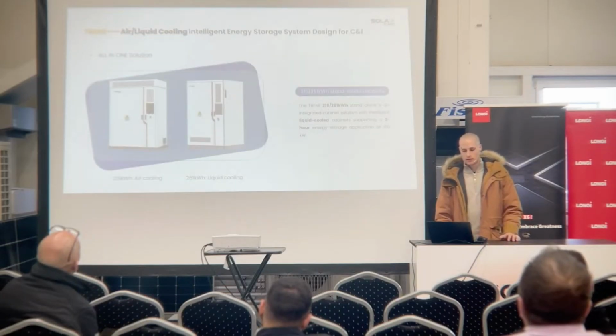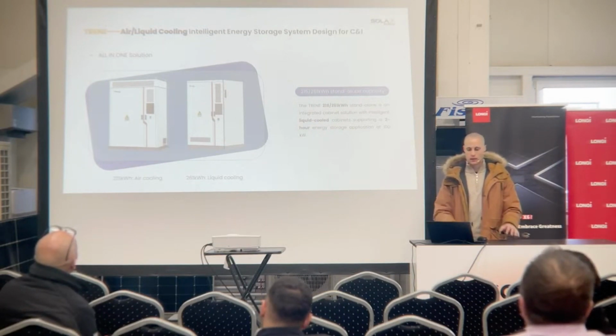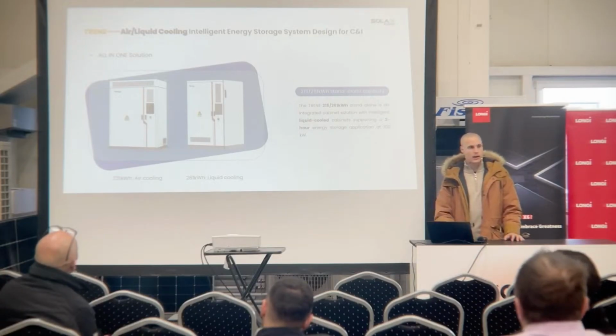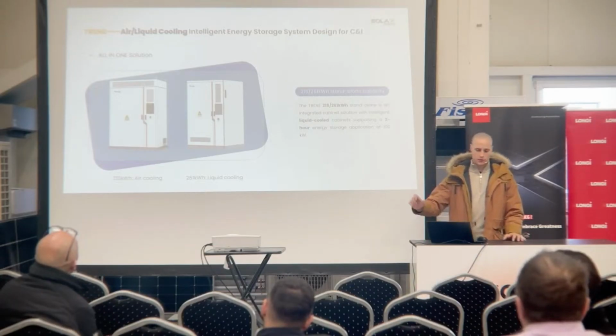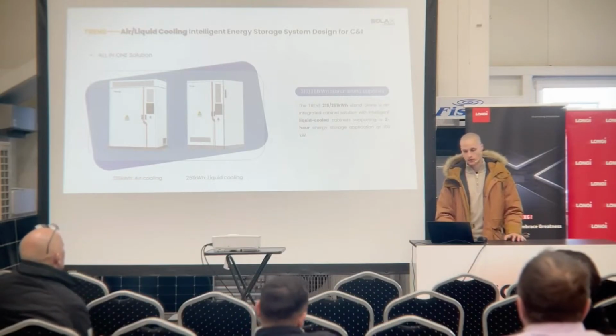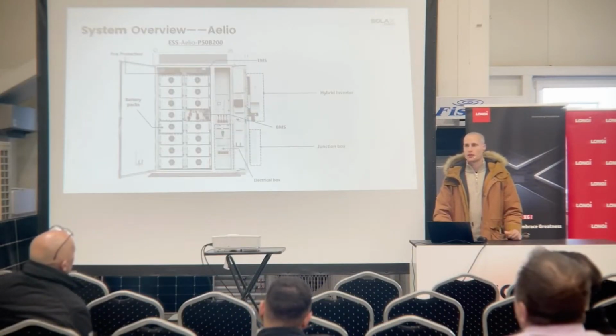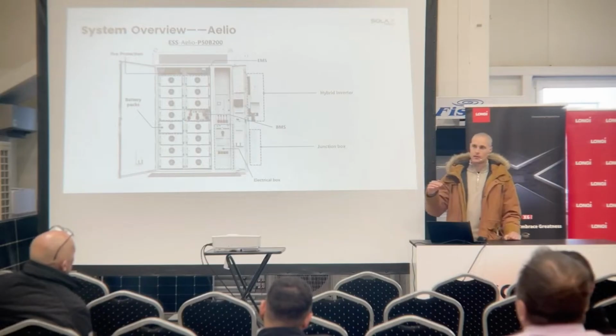For AC coupled solutions, it's called the Trena. It's 215 or 260 kilowatt hour based on whether it's the liquid or air-cooled version. The PCS size also varies depending on if it's liquid or air-cooled. Basically it's the same as the Luna, you just connect the AC and it's going to work. Price is cheaper than Huawei. So basically, on a scale, Deye will be the lowest, then Solax, then Huawei — that's roughly the pricing for them.